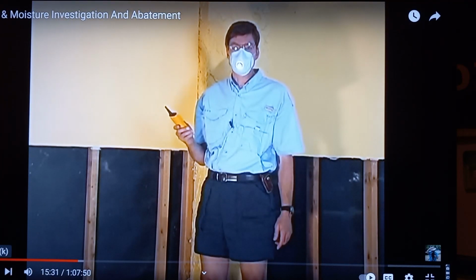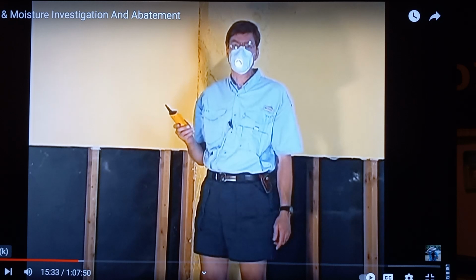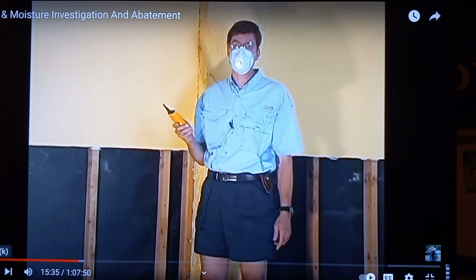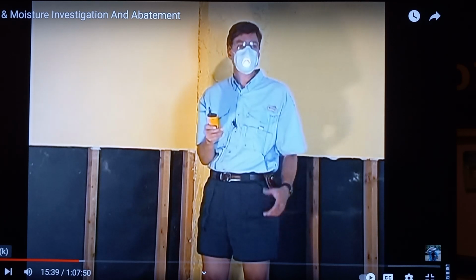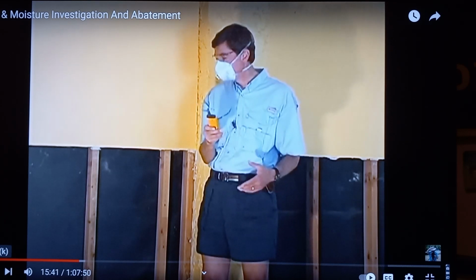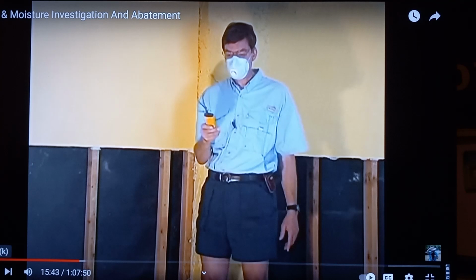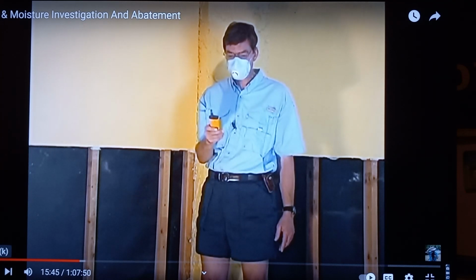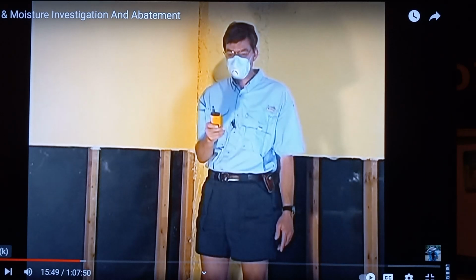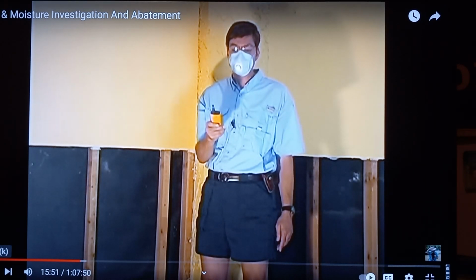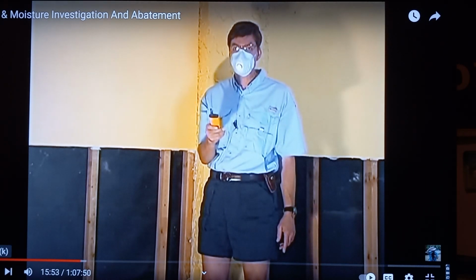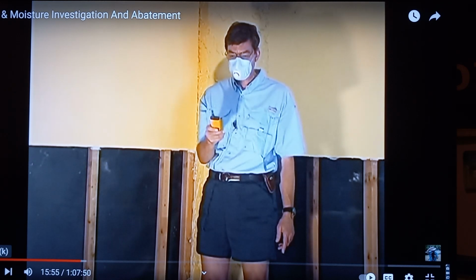I use a temperature and humidity sensor to measure the temperature and relative humidity inside and outside. This place has a musty odor and visible signs of mold growth. The temperature in here is 79 degrees. The relative humidity is 70%. These conditions are favorable for mold growth.